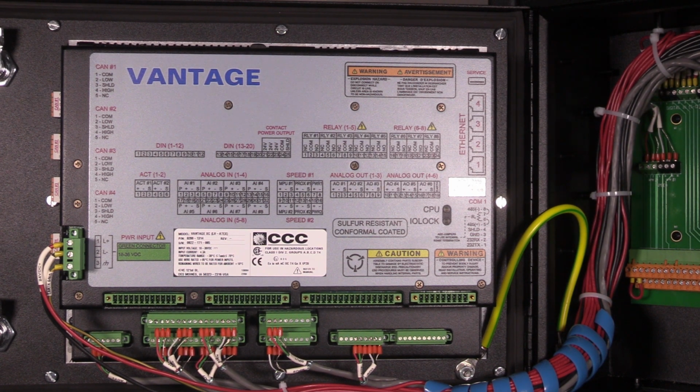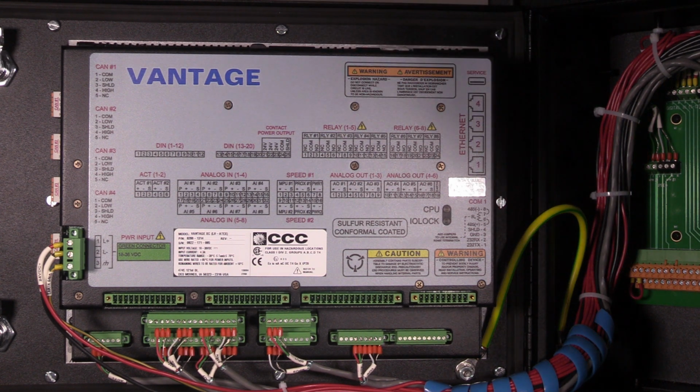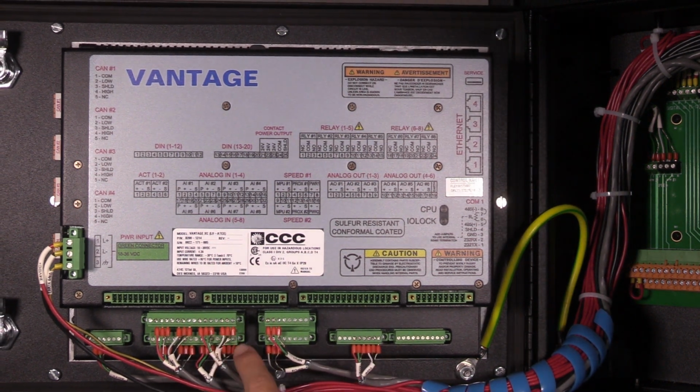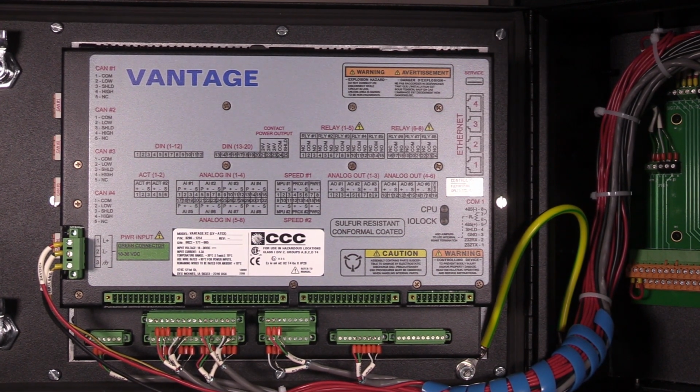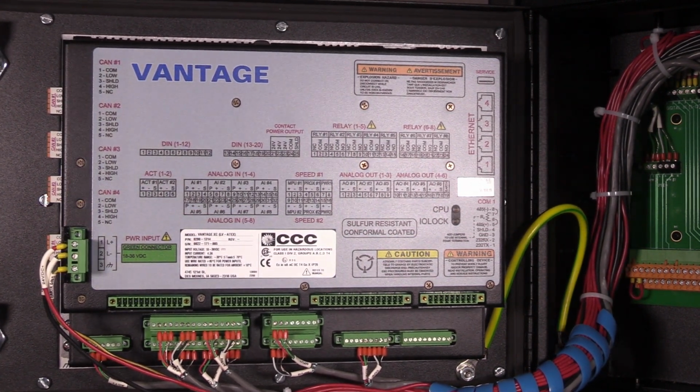We will start with wiring analog inputs. Analog input signals can be self-powered or loop-powered. Self-powered devices need no power from the control device, whereas loop-powered devices must use power from the device to function. These two types of analog input signals will be wired differently.